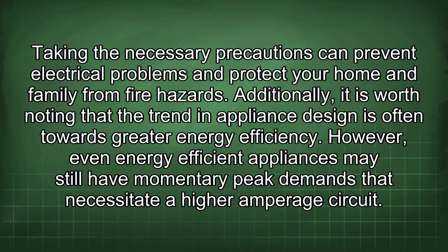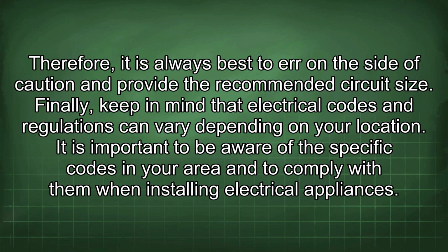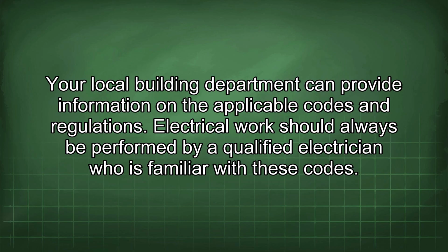Additionally, it is worth noting that the trend in appliance design is often towards greater energy efficiency. However, even energy-efficient appliances may still have momentary peak demands that necessitate a higher amperage circuit. Therefore, it is always best to err on the side of caution and provide the recommended circuit size. Finally, keep in mind that electrical codes and regulations can vary depending on your location. It is important to be aware of the specific codes in your area and to comply with them when installing electrical appliances. Your local building department can provide information on the applicable codes and regulations. Electrical work should always be performed by a qualified electrician who is familiar with these codes.